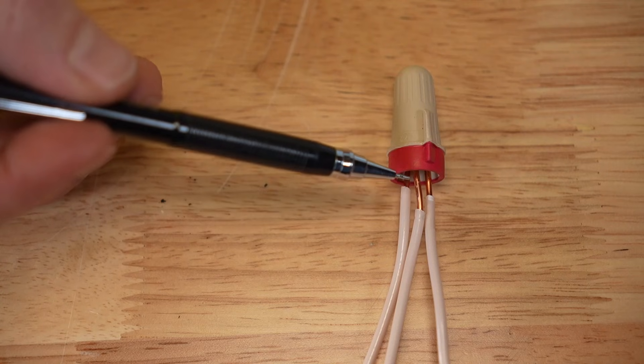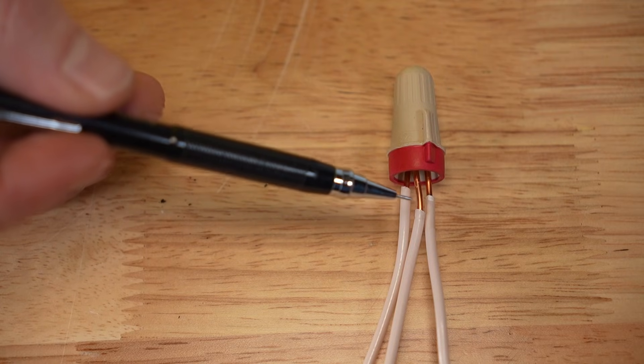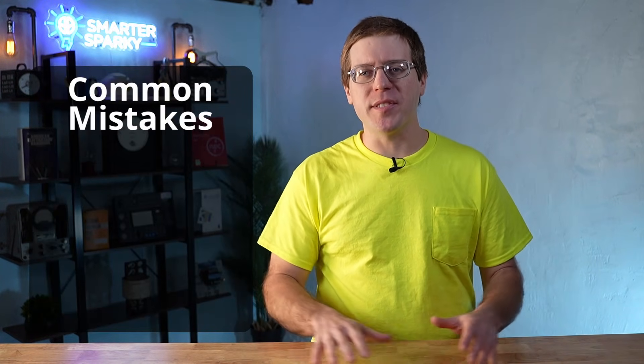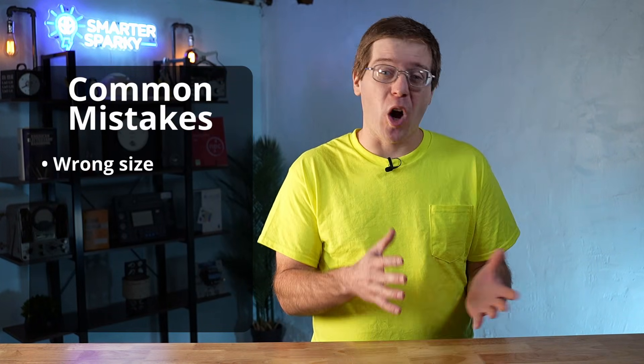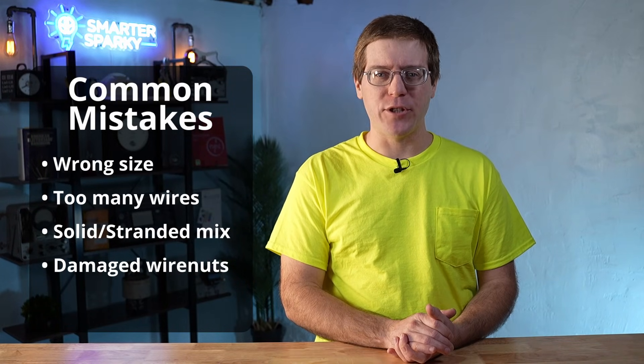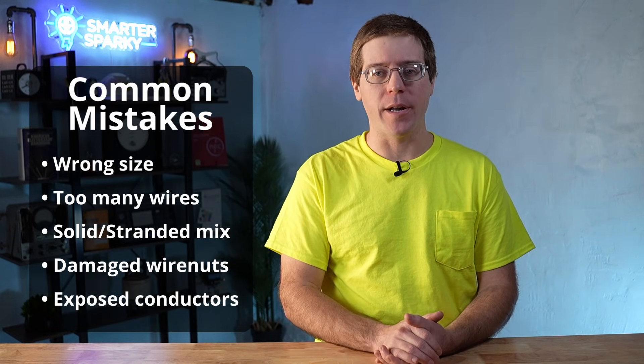You should also perform a visual inspection to ensure that no bare copper is exposed beyond the bottom of the wire nut and that no insulation is pinched up inside the wire nut. Some common mistakes with wire nuts include using the wrong size, putting too many wires in, mixing solid and stranded conductors incorrectly, reusing damaged or stretched out wire nuts, or leaving exposed copper beyond the bottom of the wire nut.